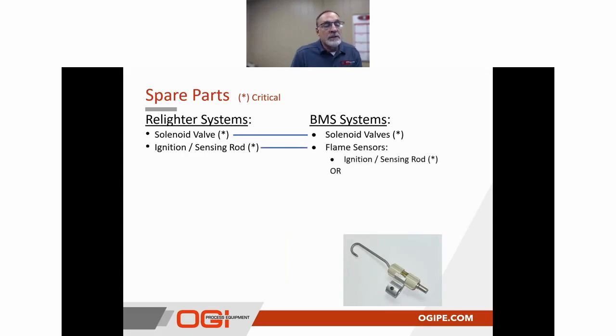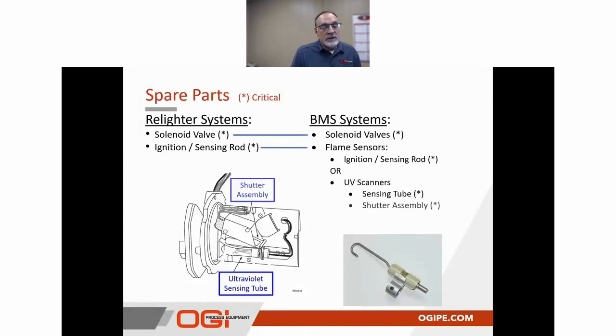The next is ignition and sensing. There's that igniter rod again. In some cases where we're going to a burner management system employed on a power burner, or maybe a more elaborate natural draft heater or burner, you'll actually have a UV scanner, where it's important to have both the ultraviolet sensing tube and the shutter assembly on hand as spare parts. Those are typically the ones that are operating the most, and if either one of them fails, the heater will be shut down.